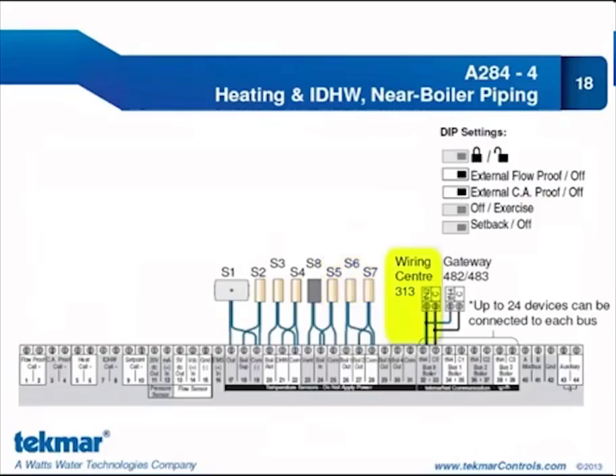The wiring center 313 is connected to boiler bus B — we have four bus terminals on the 284 and could have connected the 313 to any of them. The gateway 482/483 is connected to the same bus because for point-to-point communication, the gateway must be tied to the same bus as the thermostats. Because we have four buses and can connect up to 24 devices on each, that means up to 96 devices total, allowing for large commercial systems. Note that it is boiler bus only — we cannot accommodate any mixed buses on the 284.